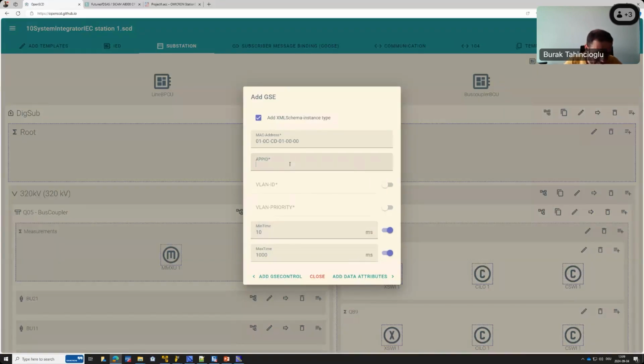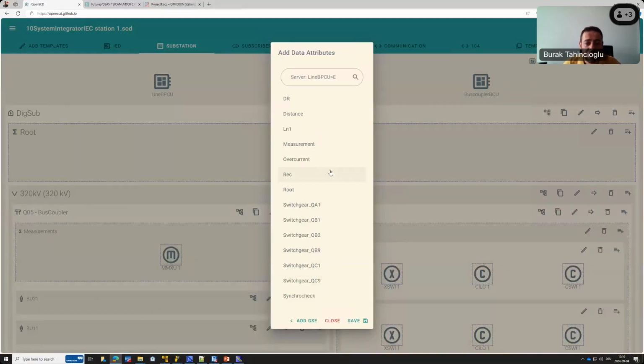The communication parameters of the GOOSE are also important to engineer in a way that they are unique, distinctly identifying the application itself. Then the tmin and tmax: if you consider this is trip information I'm sending out, maybe it's a good idea to decrease this, not use the defaults, and set tmin to 2 milliseconds. These are some design details I just wanted to mention. But now, coming to the data attributes.